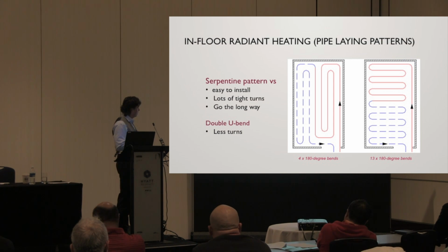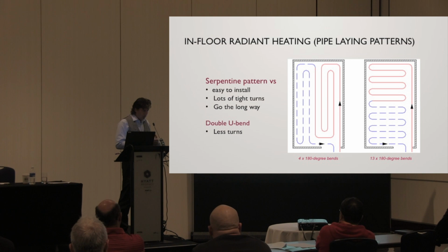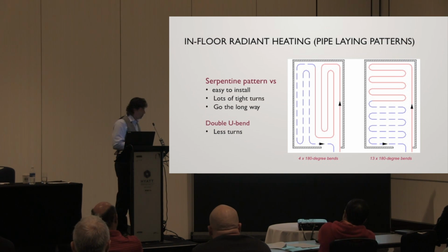And, as far as the water flow goes, when you do bend the pipe, every pipe has a designed bending radius, and it's published. Uponor, Watts, Rehau, they all say this is what your turning radius can be, and it'll be so many times the diameter of the pipe. So you have to maintain that. If you see people doing 4-inch centers with 1/2-inch pipe, they've already negated the warranty of the pipe. It's too tight. And so the ends are going to compress a little bit. That's going to compromise your flow. Pumping energy goes up, and so forth. So this kind of thing is good.